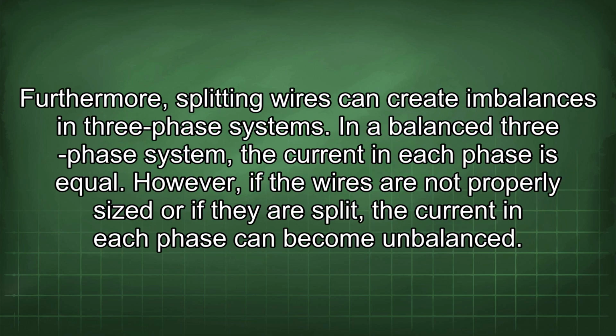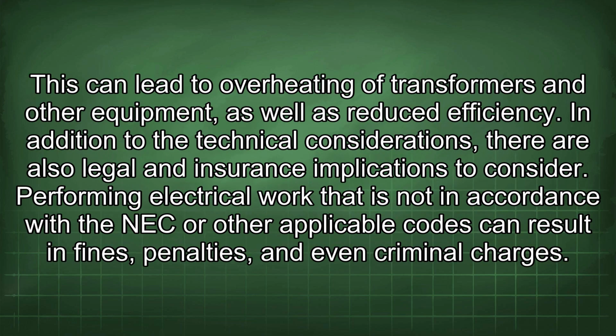Furthermore, splitting wires can create imbalances in three-phase systems. In a balanced three-phase system, the current in each phase is equal. However, if the wires are not properly sized or if they are split, the current in each phase can become unbalanced. This can lead to overheating of transformers and other equipment, as well as reduced efficiency.